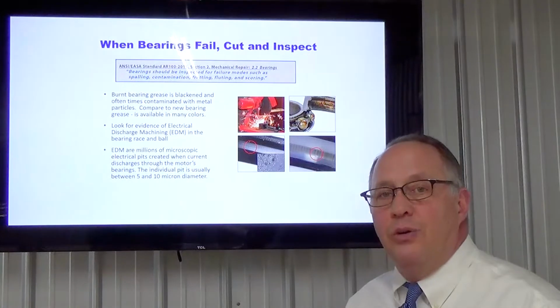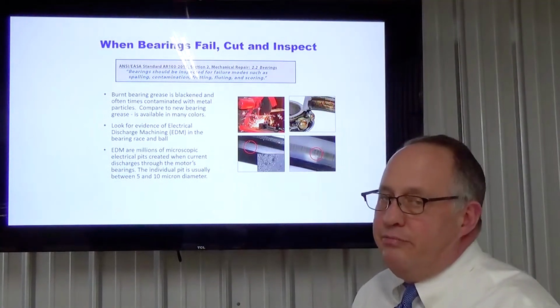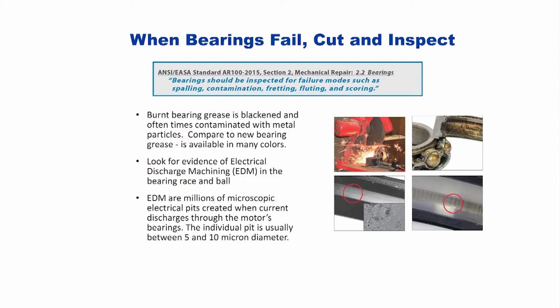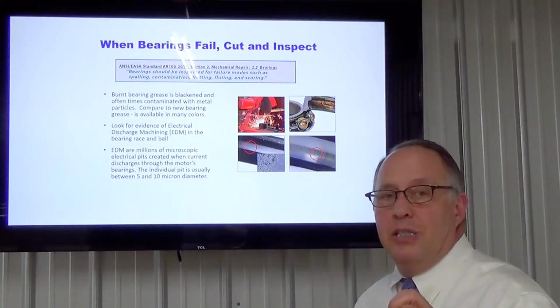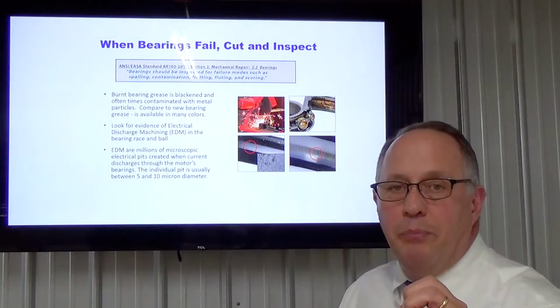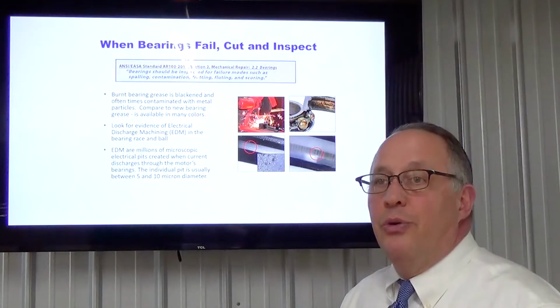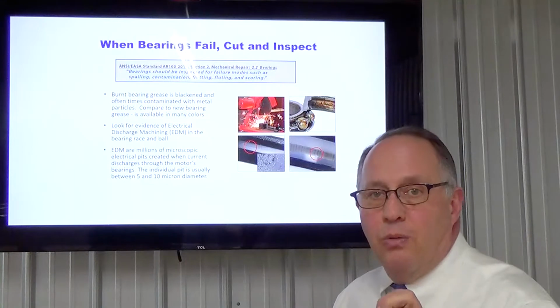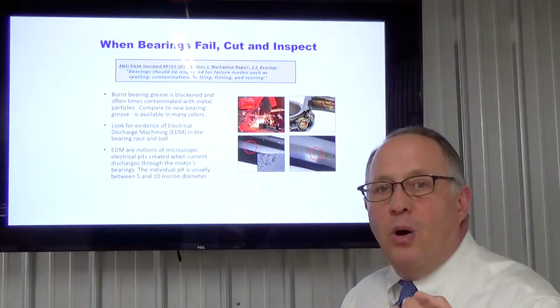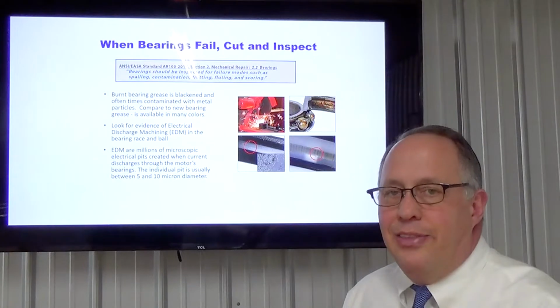When we had something fail, if you take the bearing, the motor's failed, you know there's a problem. So if you take the bearings and you cut them open, just slice them open like we've seen, you will see grease that is burnt. And then you'll start to see frosting and fluting along the way. You look for the evidence of EDM in the bearing race and ball itself. Actually, I didn't mention this earlier, but the ball will develop pits and damage as well. So now you did have a nice round smooth ball, and now you've got a ball with pits and damage in it, so obviously that gets to be a problem as well.